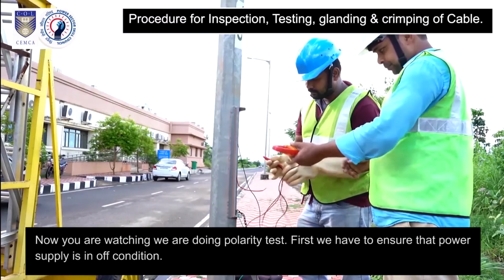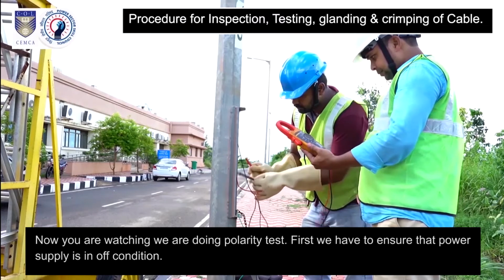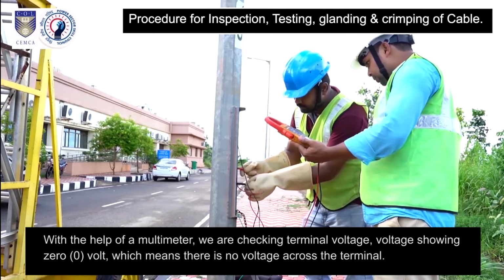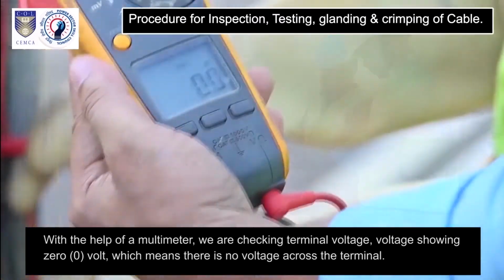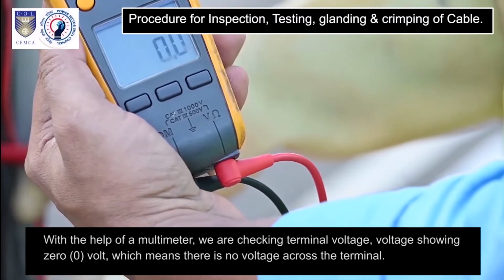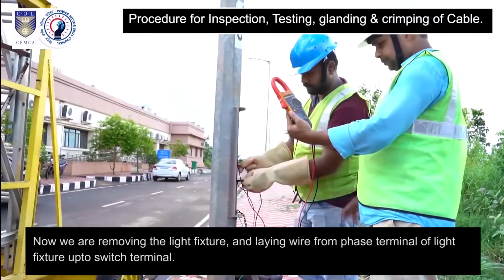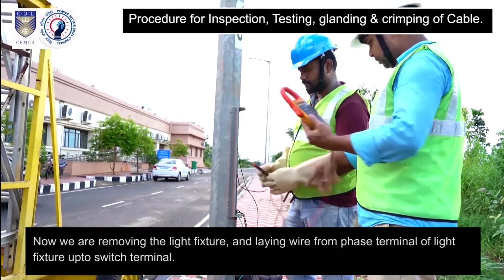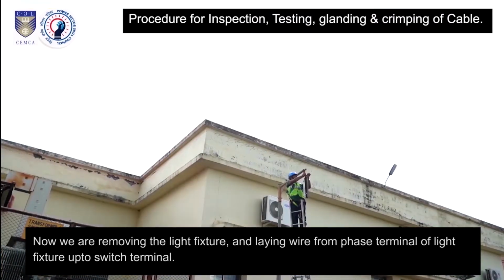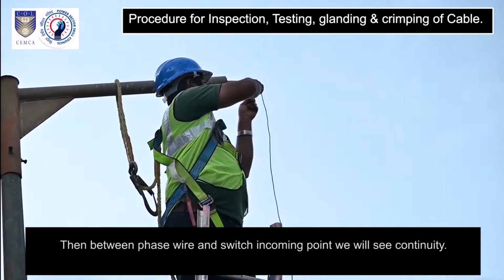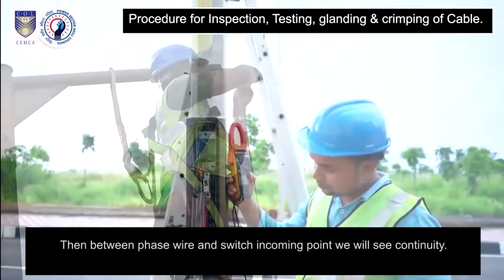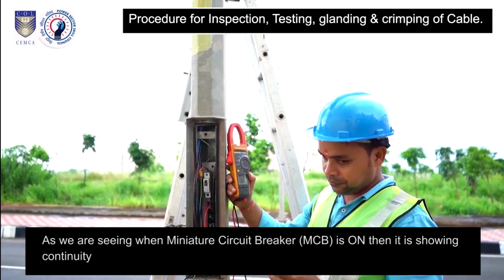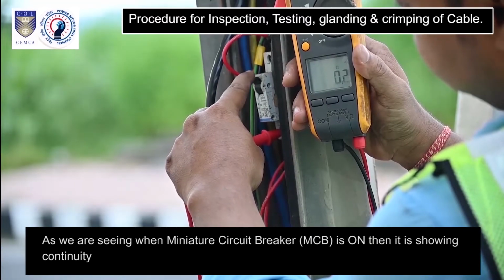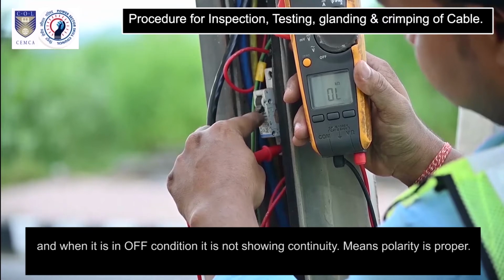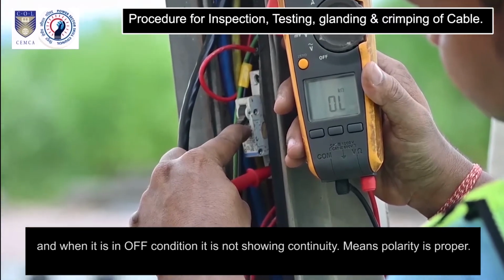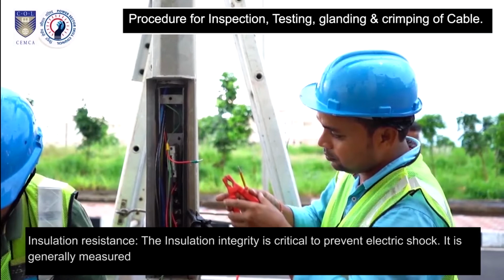Now you're watching we are doing polarity test. First we have to ensure that power supply is in off condition. With the help of a multimeter, we are checking terminal voltage showing 0 volt, which means there is no voltage across the terminal. Now we are removing the light fixture and laying wire from phase terminal of light fixture up to switch terminal. Then between phase wire and switch incoming point we will see continuity. As we are seeing, when miniature circuit breaker MCB is on, then it is showing continuity, and when it is in off condition, it is not showing continuity. Means polarity is proper.